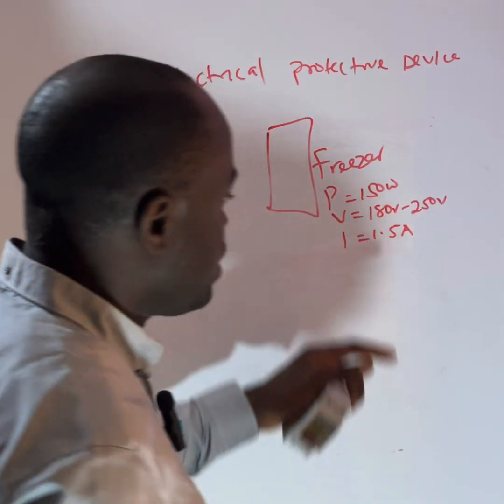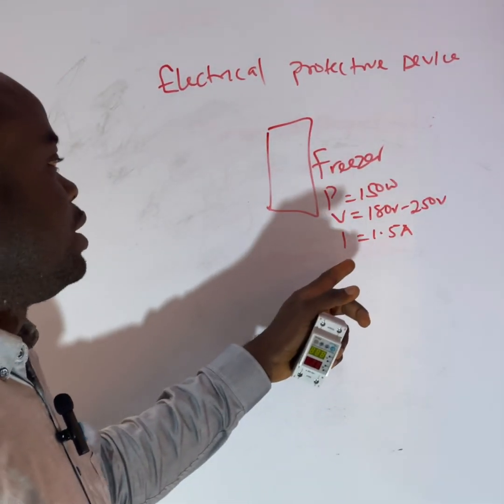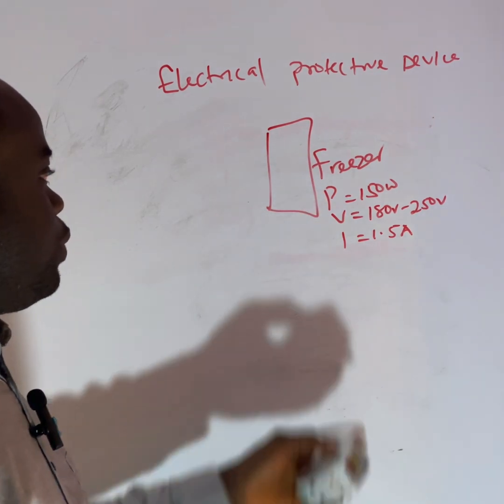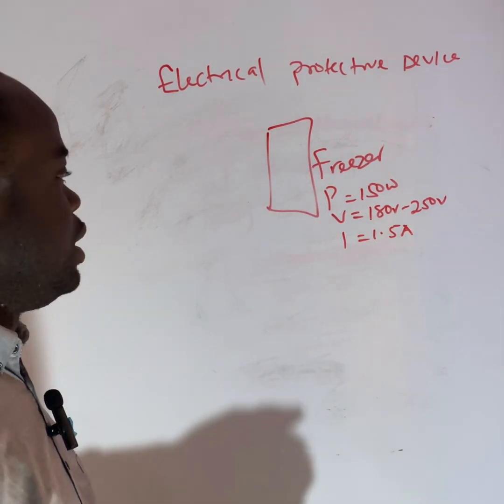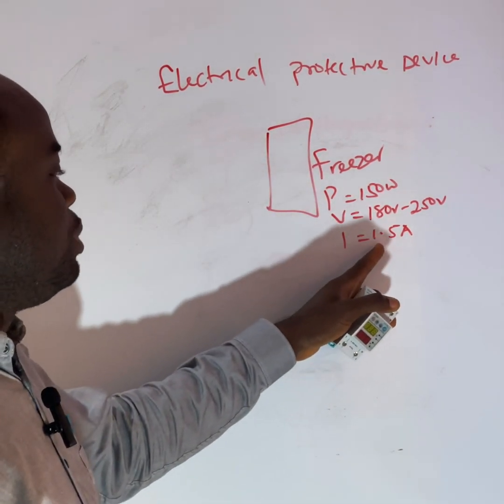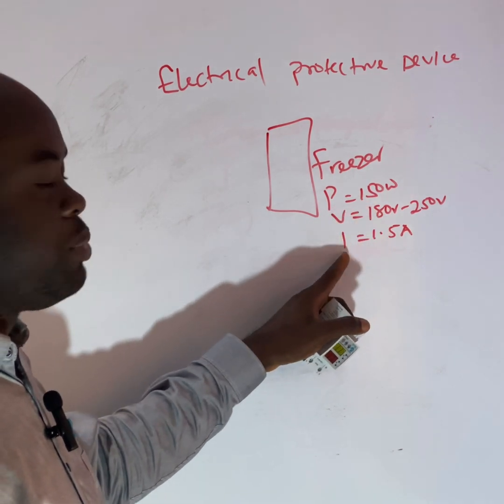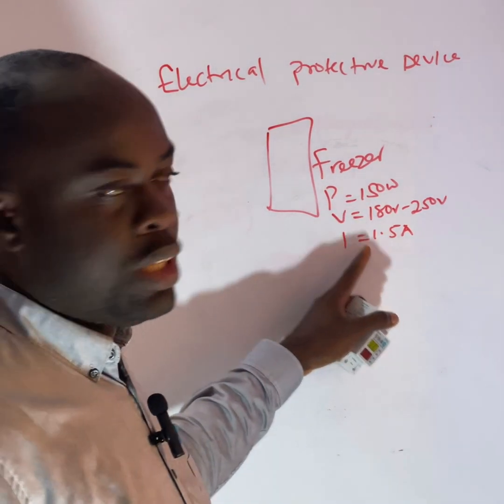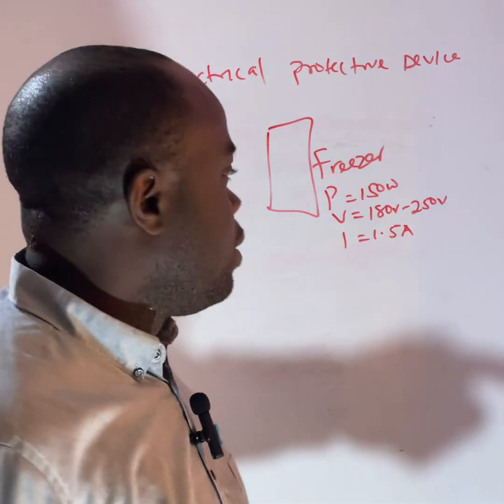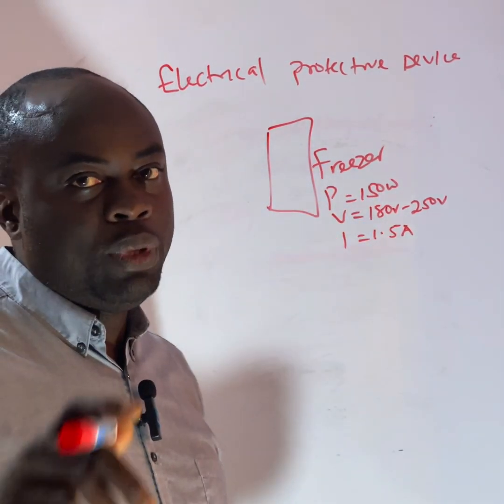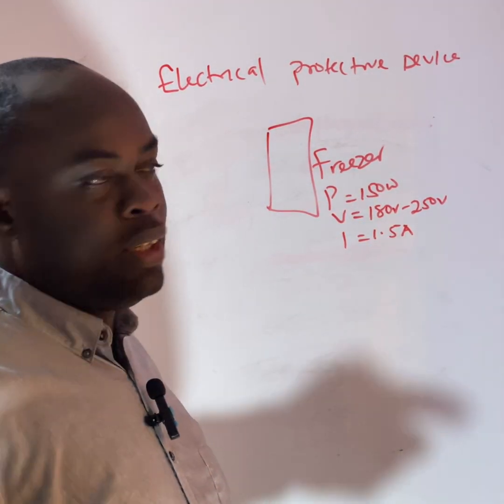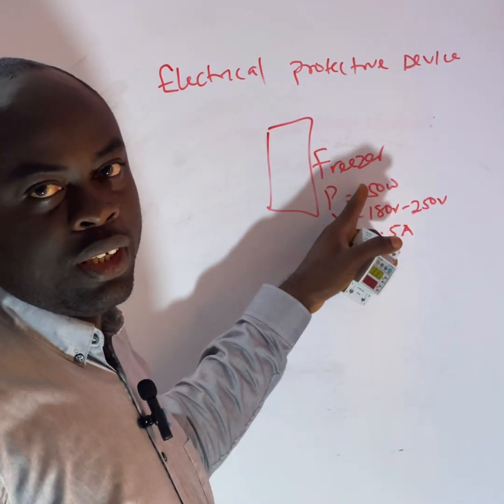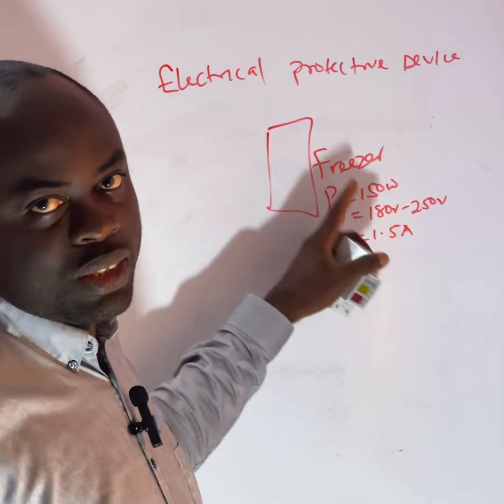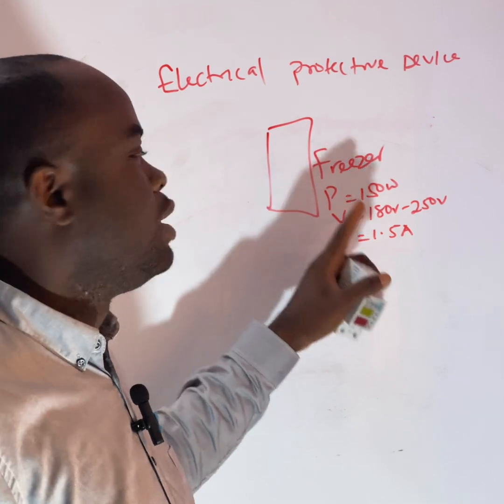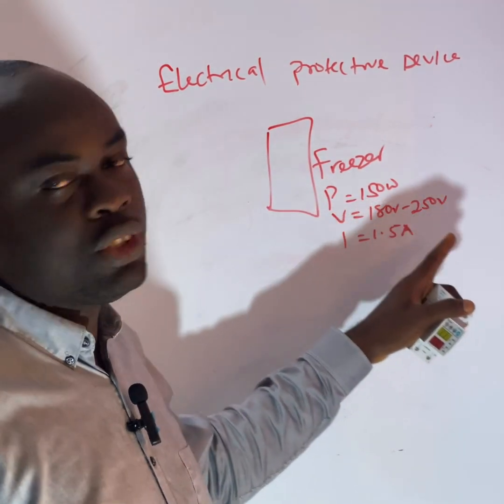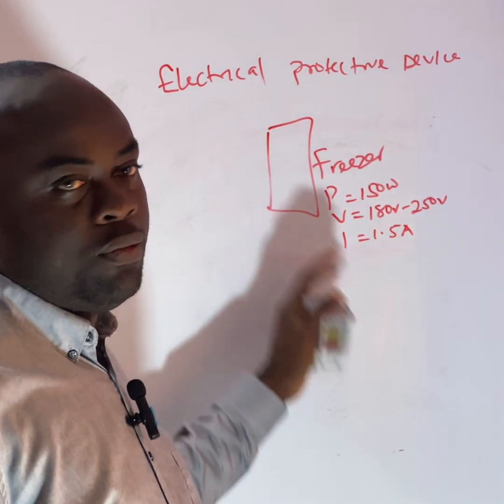Now this information is very key and important for the protection of the equipment. It means that whatever comes into the equipment above, for example, 1.5 amps will damage the freezer. Whatever input power supplied to it that is more than 150 watts will damage the freezer. And whatever voltage is above this range will damage the freezer.